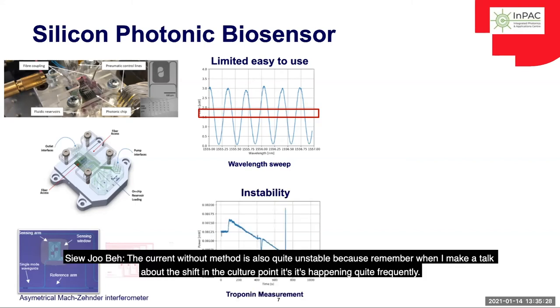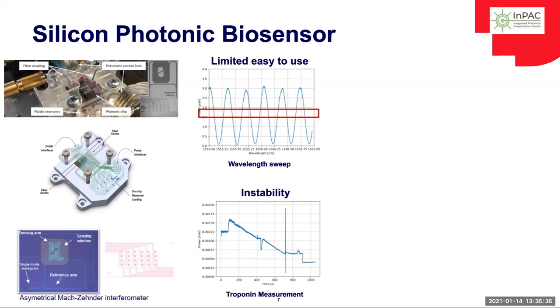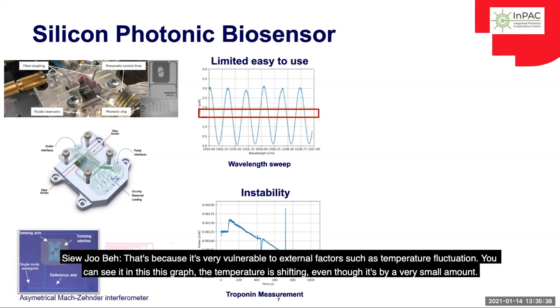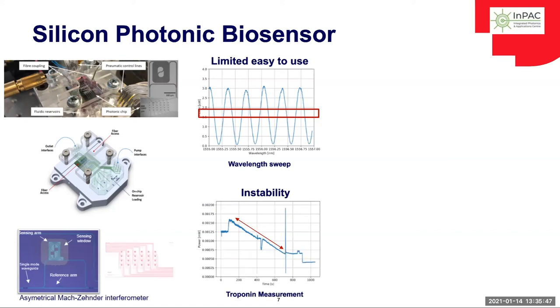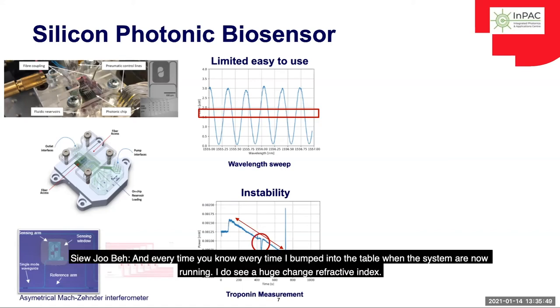The current readout method is also quite unstable, because the shift in the quadrature point happens quite frequently. That's because it's very vulnerable to external factors such as temperature fluctuation. You can see in this graph the temperature was shifting even though by a very small amount. Every time I bump into the table while the system is running, I see a huge change in refractive index.